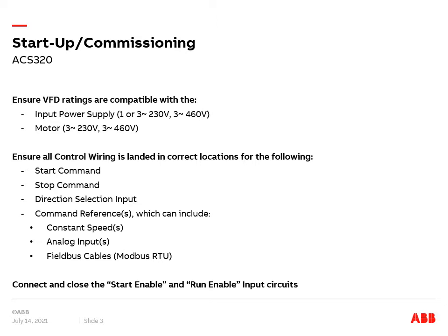Control wiring must also be landed in the correct locations on the VFD terminals. The primary locations required to operate a VFD are a start command, stop command, and speed reference. Additionally, a direction selection input, constant speed or frequency inputs, analog inputs, and field bus cables can also be connected.